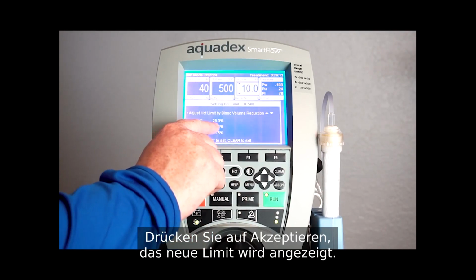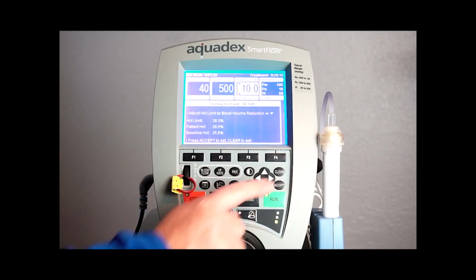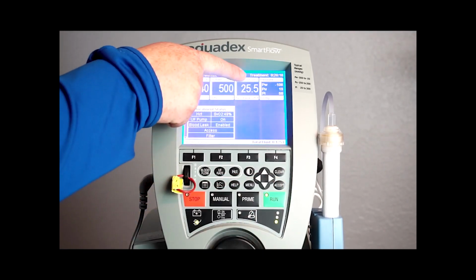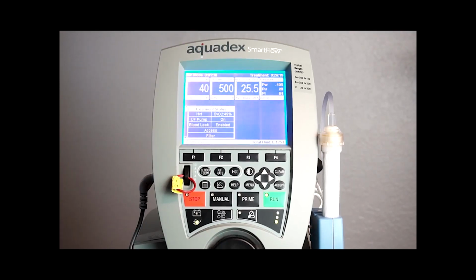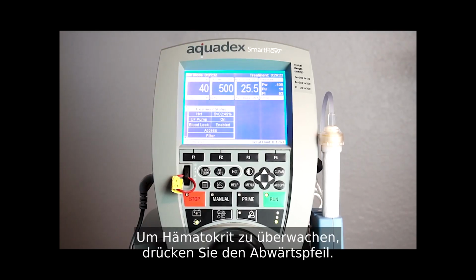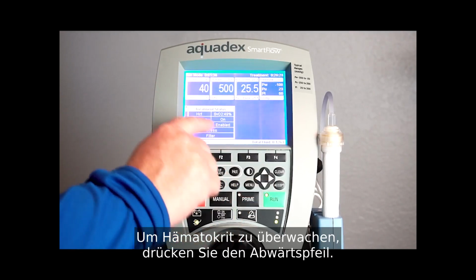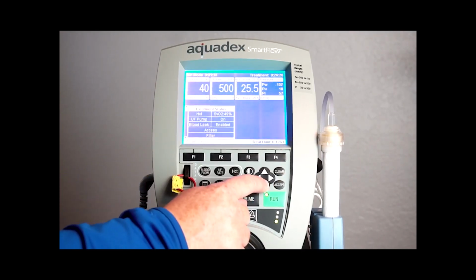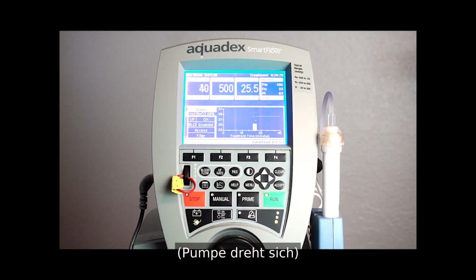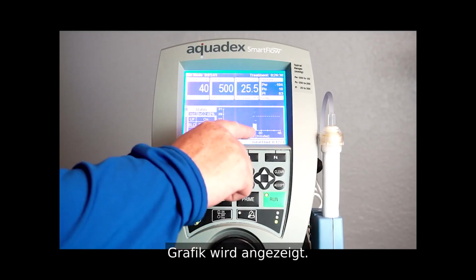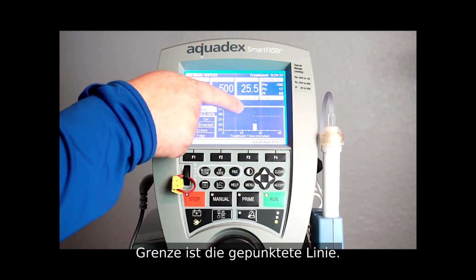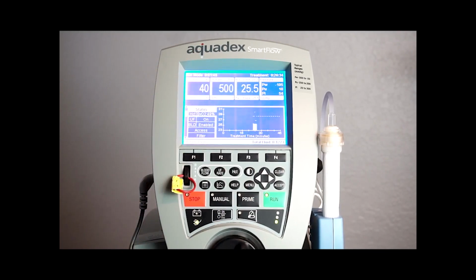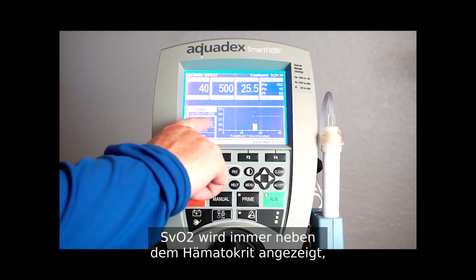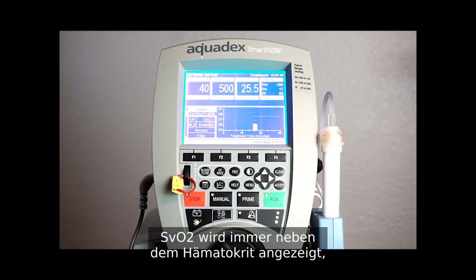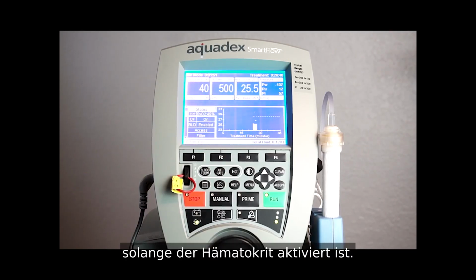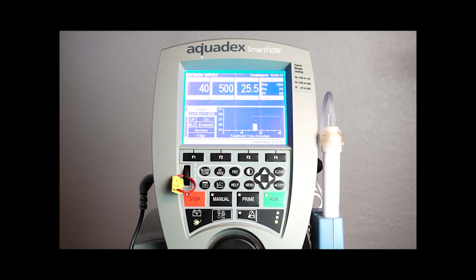New limit will be displayed. To monitor hematocrit, press the down arrow to highlight. Graph will be displayed. Limit is the dotted line.